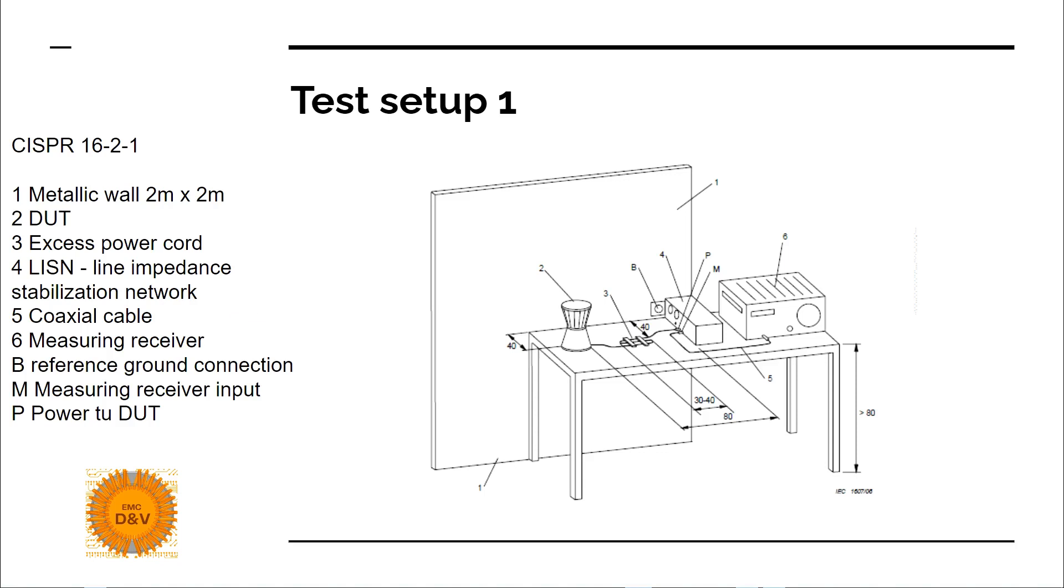Your measurement equipment is a spectrum analyzer with a 50 ohm termination connected to the LISN. The spectrum analyzer will measure the common mode plus minus differential mode noise and display it on a graph with the limit lines we saw earlier. An important part of the test setup is maintaining the distances, as they will make the test repeatable in any location.